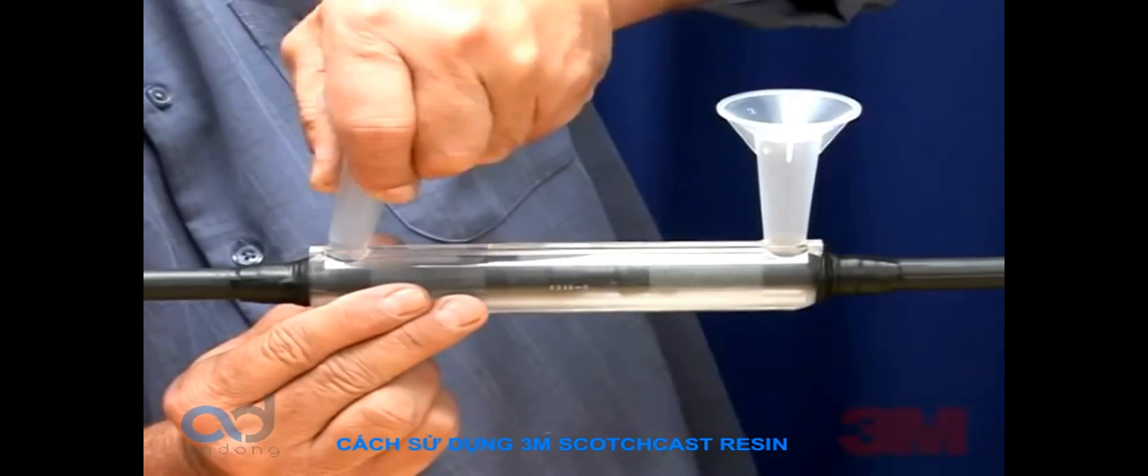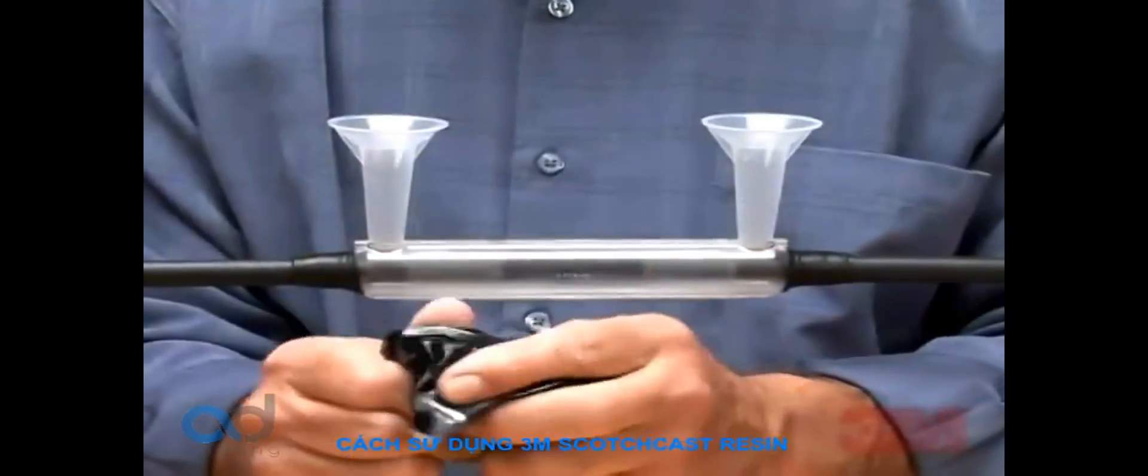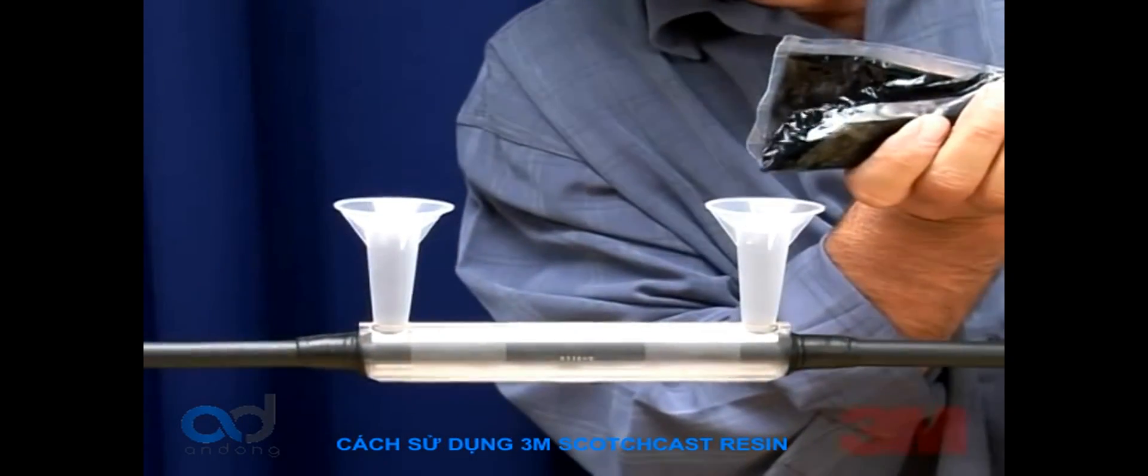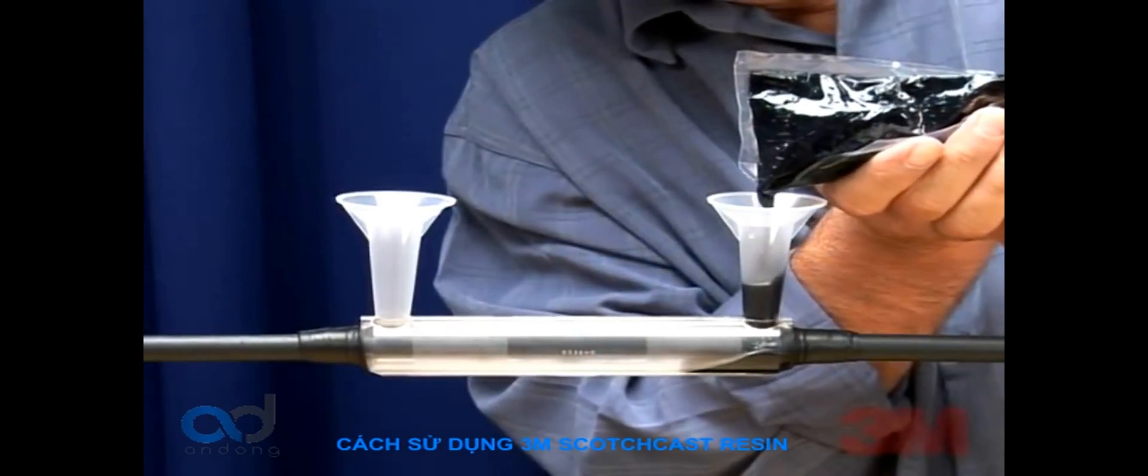Step 4: Put the pouring spouts in the holes. Make sure the splice position is level. Mix the resin thoroughly according to the instructions on the resin package. Pour the resin immediately after mixing. Fill only through one spout until both spouts are completely filled.